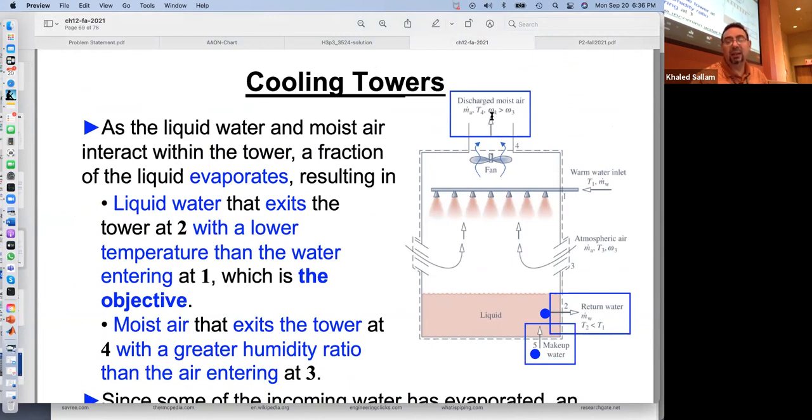But basically it ties the omega exit with the temperature of the water and the temperature of the air. Because when you think about it, m dot h in plus m dot h in, water in and air in, equals m dot water leaving and h water leaving. So if you specify, I want you to cool it by 5 degrees, for example, the only unknown in that equation will be how much is the energy out. Okay? And that will allow you to get the omega. Questions?